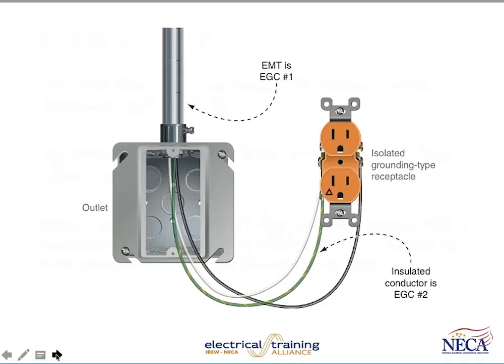So the graphic that you see is typical of what you would see in a patient care space, a branch circuit for the patient care space. The concepts in 517.13(A) and (B) are all about not having all of your eggs in one basket. You want to have two equipment grounding conductor paths. Path 1 is the metal EMT in this case. Path 2 is your contained insulated equipment grounding conductor that connects to the receptacle.